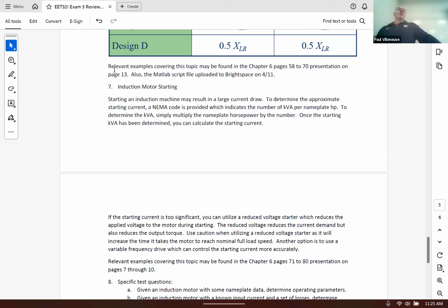But how do you know that a system can't handle starting a motor? Voltage drops, right? If I'm pulling 10,000 amps and I got a transformer and wire that has impedances associated with it, if I pull so much current, those impedances cause me to get greater than a 10% voltage drop across the motor, it's possible that the motor won't start.